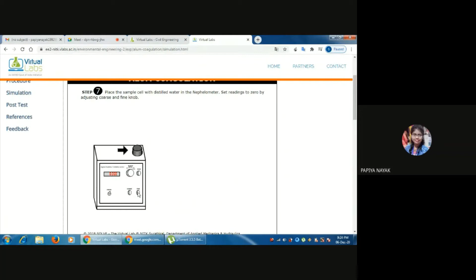So first we switch on the system, and then we place the sample cell. This is the sample cell, which is called the nephelometer tube, filled with distilled water. First we place this nephelometer tube in the nephelometer. Yeah, the value is 0.030. Now we set the reading to 0 by adjusting the coarse and fine knobs. Now the value is 0.